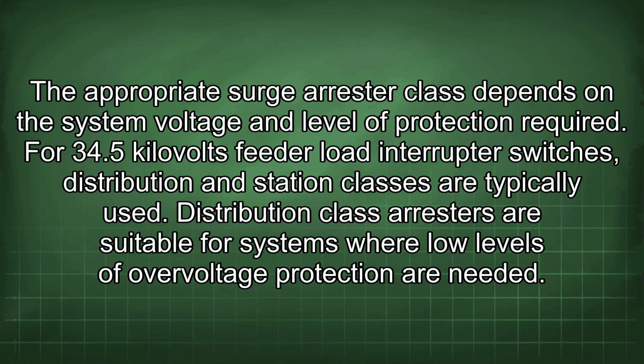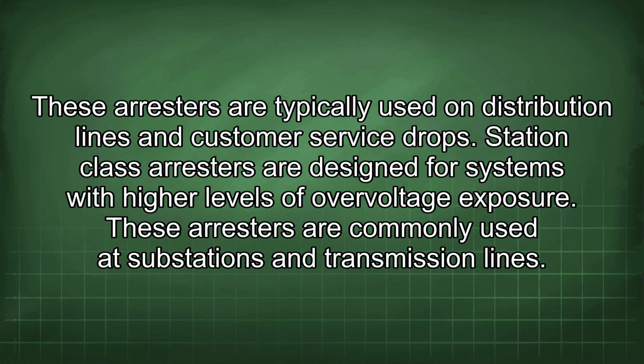For 34.5 kV feeder load interrupter switches, distribution and station classes are typically used. Distribution class arresters are suitable for systems where low levels of overvoltage protection are needed. These arresters are typically used on distribution lines and customer service drops. Station class arresters are designed for systems with higher levels of overvoltage exposure. These arresters are commonly used at substations and transmission lines.